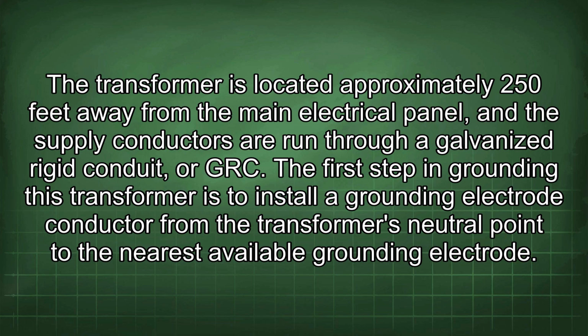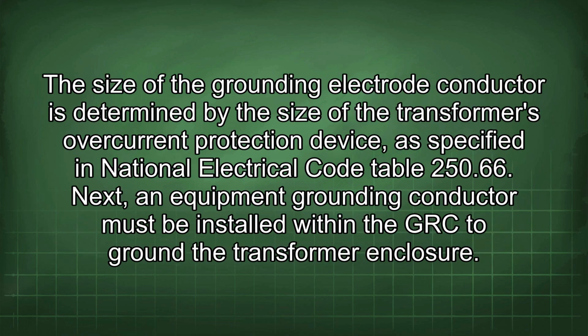The first step in grounding this transformer is to install a grounding electrode conductor from the transformer's neutral point to the nearest available grounding electrode. The size of the grounding electrode conductor is determined by the size of the transformer's overcurrent protection device, as specified in National Electrical Code Table 250.66. Next, an equipment grounding conductor must be installed within the GRC to ground the transformer enclosure.